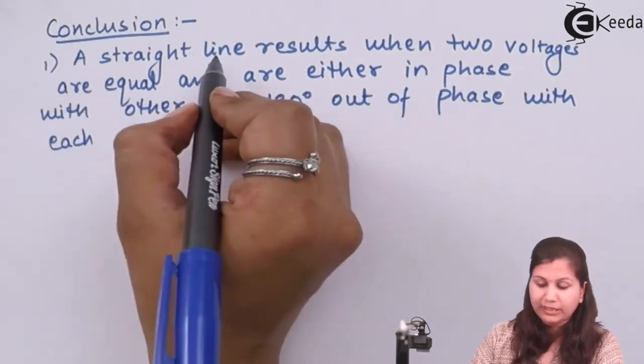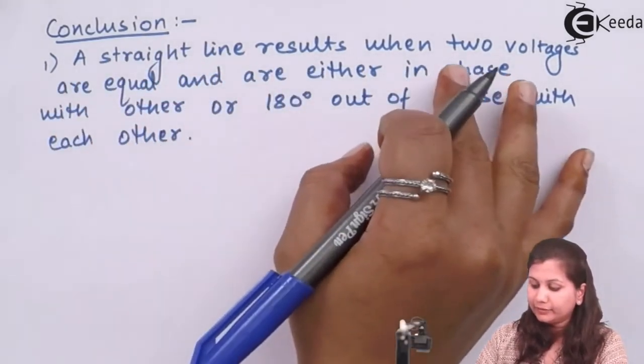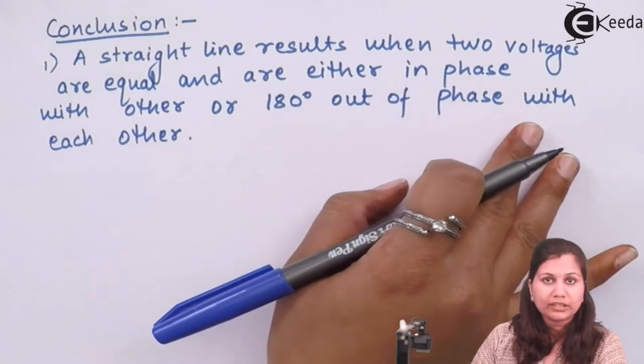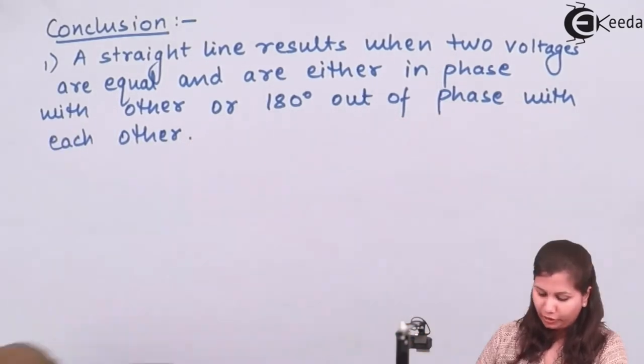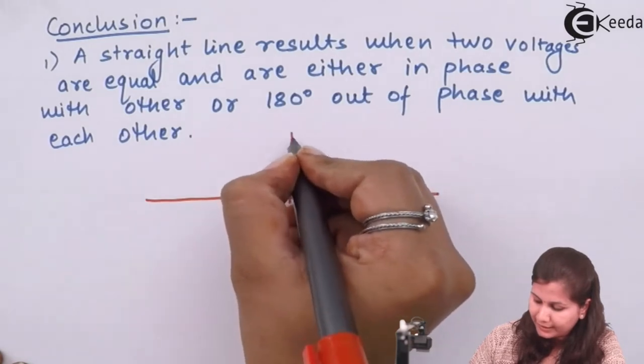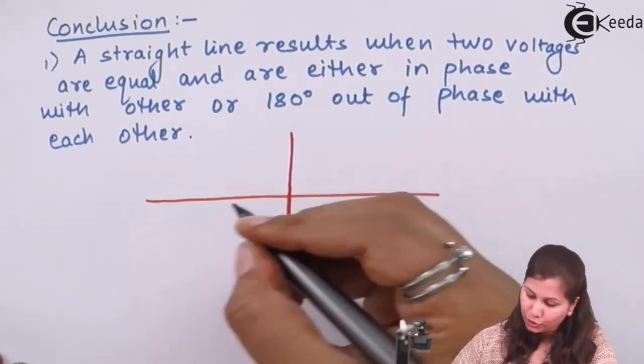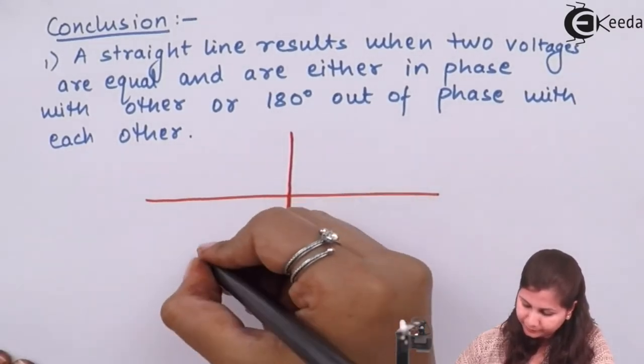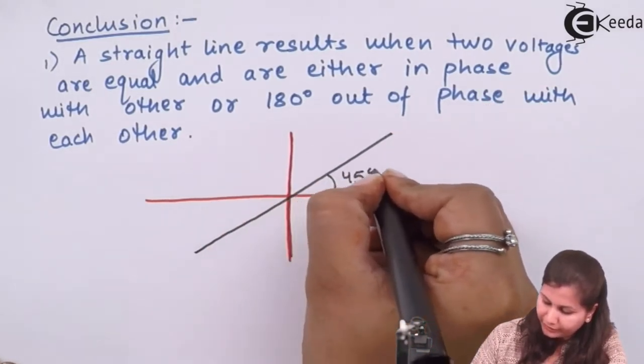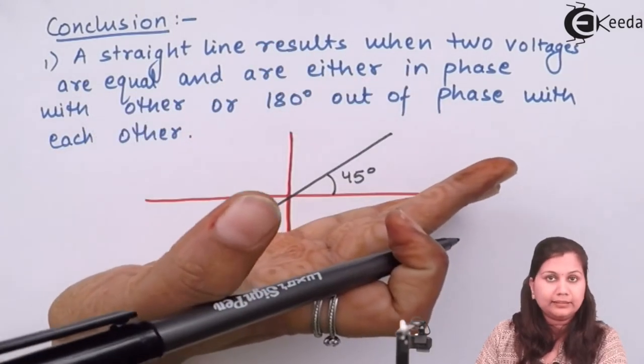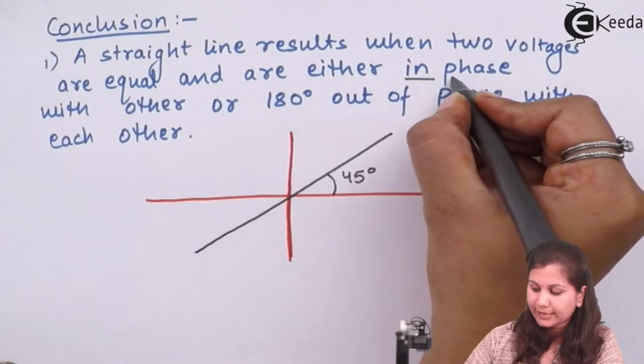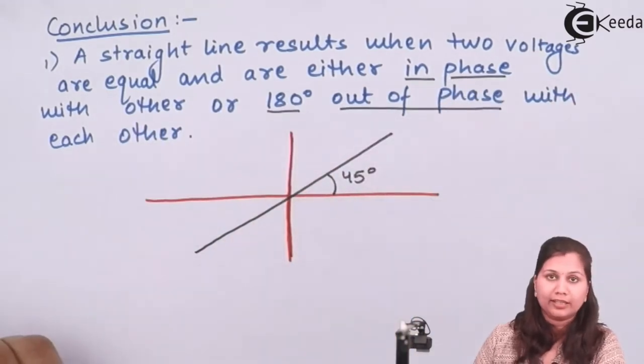When a straight line is obtained as a Lissajous pattern, the two voltages are equal, they have equal frequency, and they are either in phase with each other or 180 degrees out of phase with each other. On the CRO screen, this straight line makes an angle of 45 degrees with the horizontal. It can be tilted in either direction depending on whether the signals are in phase or 180 degrees out of phase with each other.